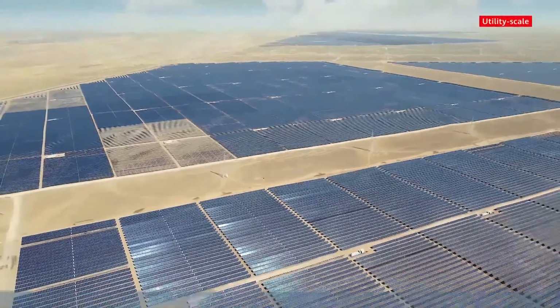Around the world, there are a lot of areas without access to mains or that only have weak mains. We provide an affordable off-grid PV solution that replaces diesel generators. There are about 50 million diesel generators and an increment of 5 million DGs every year. The fuel cost is high, and so is the maintenance cost. The noise, the pollution, and the reliability are all big problems. The core of the off-grid PV solution is the storage, mains, and the DG, smart scheduling technologies, as well as AC and DC reliable power supply, which can reduce the power generation cost by 60%, and it can replace the traditional DG to protect the environment.